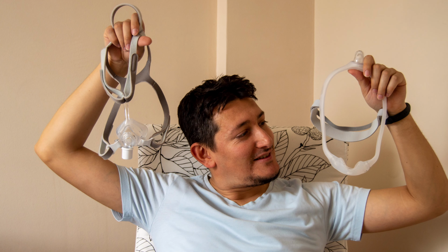So it works in the opposite way. If you take your mask off, it knows that the ambient pressure in the air has decreased sharply. And after a couple of seconds, usually if this setting is turned on anyway, it will turn off automatically. So the reason your machine is turning off in the middle of the night is actually due to this setting. If you don't have a good seal with your mask, let's say for instance, you're on a nasal pillow or nasal mask, your mouth opens, you're going to have a huge leak. The air is going to rush out your mouth.